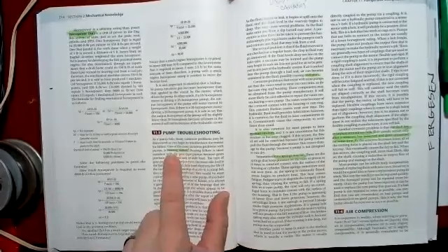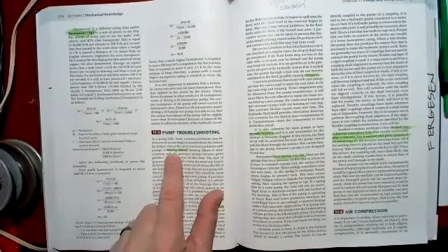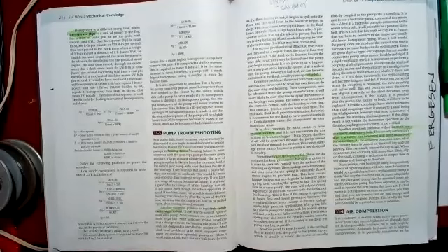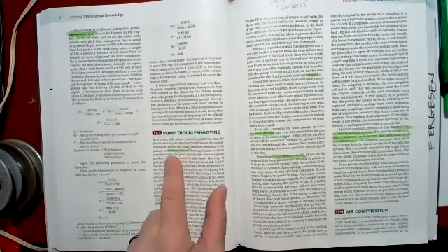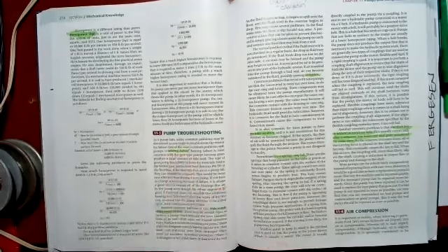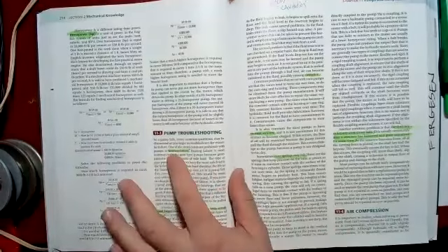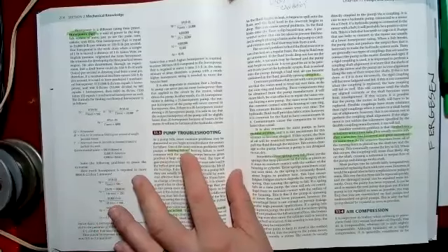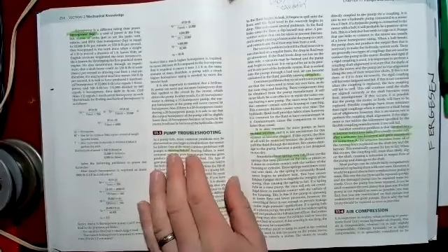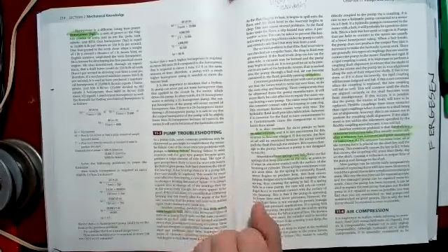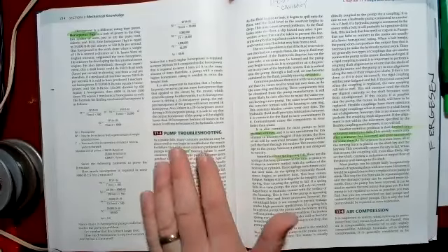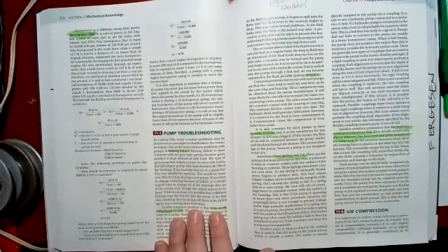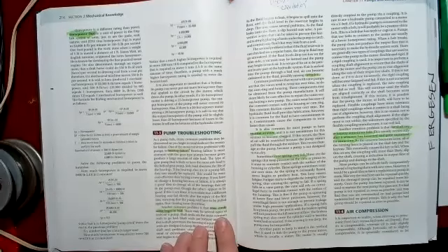The book says the number one reason for pump failure is bearing failure. And this is probably true for pumps that are well maintained on clean hydraulic systems overall. Bearing failure is the reason why it will fail over time. If they tend to run hot, the bearings will fail faster. Bearings will wear over time, even if you run the pump perfectly. So bearing failure is the most common thing. And the book goes through a couple of reasons why bearings may fail more quickly, which are good.